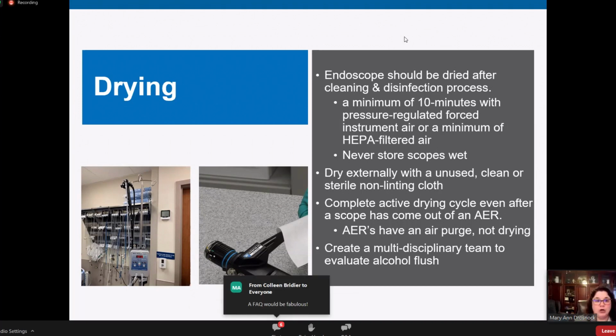We want to make sure that these scopes are completely dry prior to going into a storage cabinet or prior to being reused. And again, we had a lot of discussion around the topic of drying and when it is appropriate to completely dry and when it is not. But what we landed on is all scopes. Every scope, every time, must be completely dried with compressed air. We do recommend instrument quality air, and that's defined within the standard, at minimum HEPA filtered air for flushing. And generally we recommend 10 minutes if you're doing a process with a drying pump. We don't recommend that it's just flushing with a syringe anymore. You have to do this pressure regulated forced instrument quality, or minimum HEPA filtered, air on all scopes. So yes, that includes those coming out of an AER.